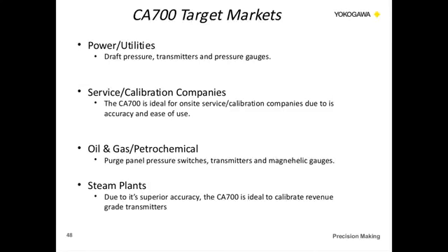So in the oil and petrochem industry, purge panel switches are very, very tough applications. Those are very small, 1 to 2 inches of water switches that customers typically have a hard time trying to calibrate. Transmitters and Magnehelic gauges are down in the low inches of water, so those are very difficult to calibrate as well.